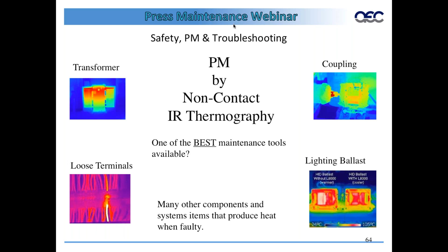Just some more examples, and it doesn't have to be electrical. The one you see here is an outdoor transformer, and maybe nothing's wrong, but you can go and take a snapshot of it, and then look at that once every 6 months, a year, whatever, just to have a baseline of how things look, and then you can easily spot if something's wrong. At the bottom, you'll see another wire with a loose connection. And then there's other things you can see too. You can see anything that's related to heat. So it could be a bad bearing somewhere. It could be a roof leak. It could be heat escaping around a door. The seals are bad. Here's some more examples of what I'm talking about here.